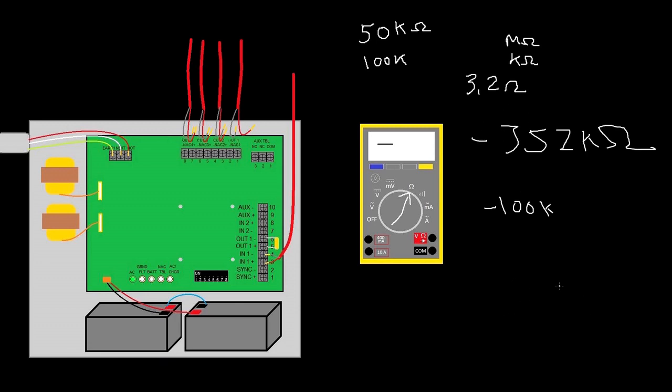So my monitor module, it's not directly touching my SLC, but through the circuitry of the monitor module it's picking up the ground or the water and that can really muddy the reading. That's maybe getting a little bit advanced, but it's just a quick tip. So I think that's where I'm going to stop here.